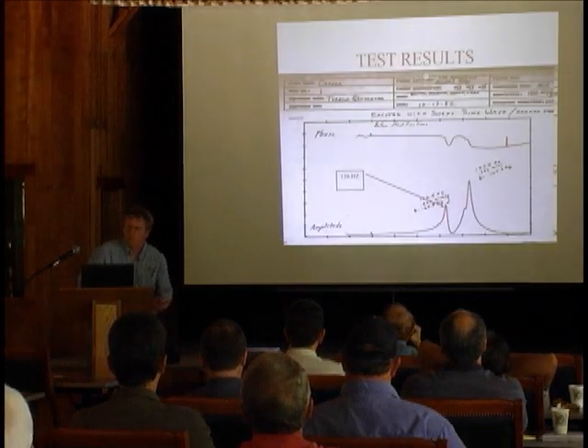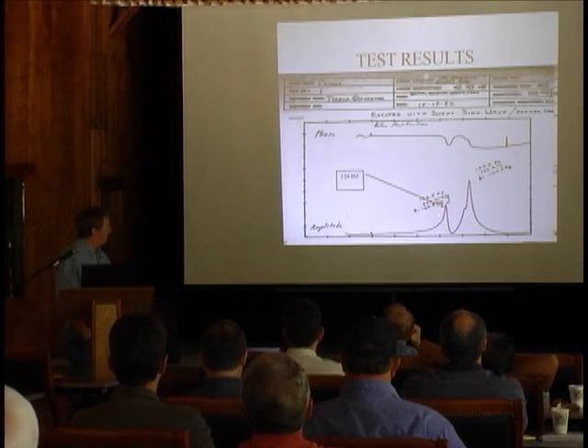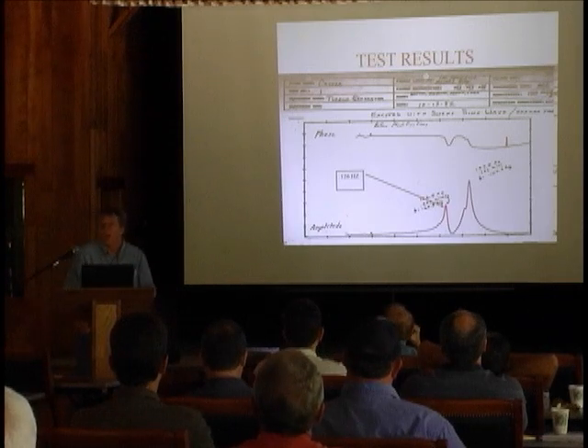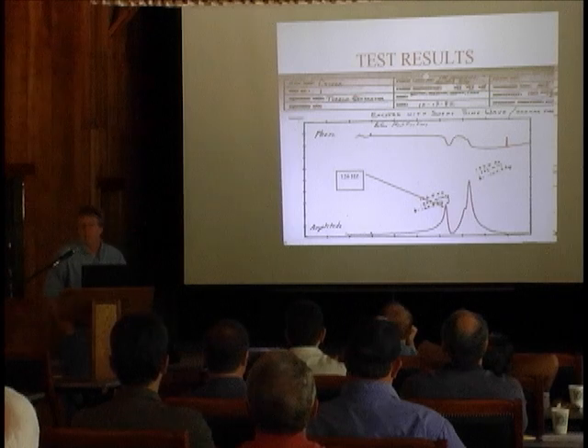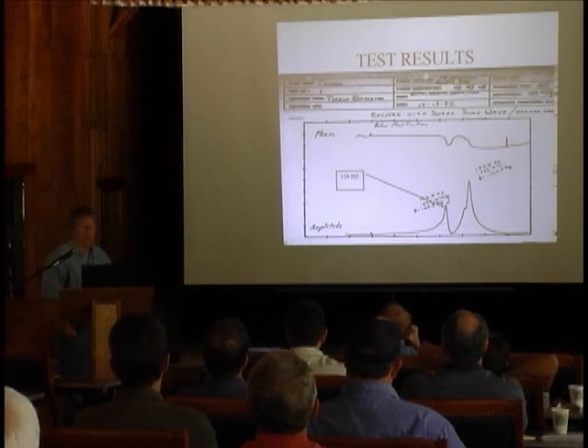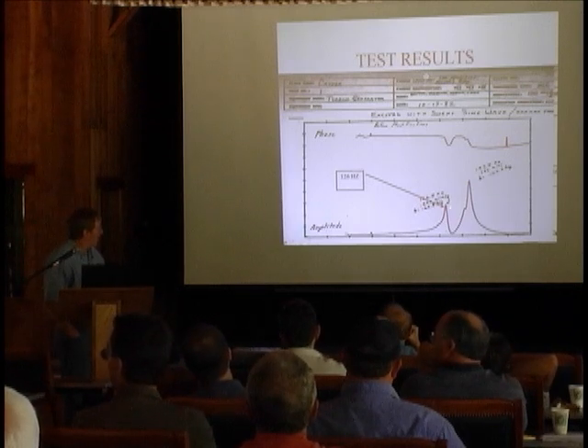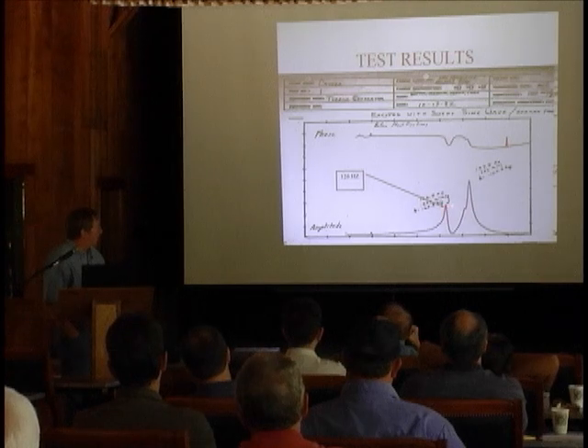And what we do, we're shaking the coils and note the natural frequency. This is one of them that's having a problem. Basically what I did, I went in every year after this and I tested all the phase leads. These were 2 Westinghouses, and they kept having problems come back, not blowing up, but we were catching them early this time. And the natural frequency is 126 hertz.